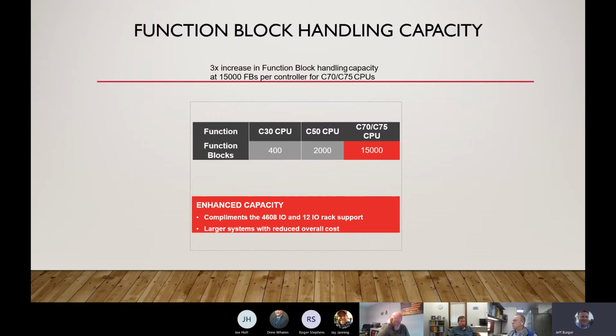The function block: you talked earlier about the different CPUs on the HC900, and depending on the CPU that you're using, it has a memory storage in there that allows you to configure a certain amount of function blocks in the configuration. So as you can see, the C30 allows 400 function blocks to be configured, a C50 is 2,000, and then when you go up to the C70 or C75 CPU, now you can have 15,000 function blocks configured. I will tell you that a program that has 2,000 function blocks, that's a pretty intricate system. Most applications that I've come across are usually around the 500 to 1,000 function block range, but you can see the capacity here. You can really do a lot with the single CPU.